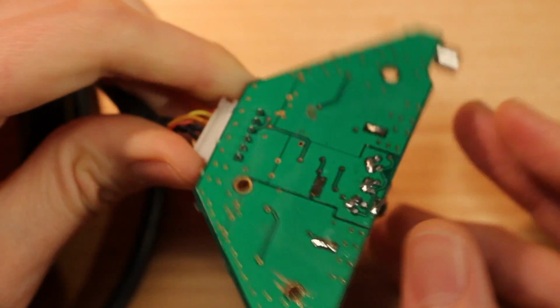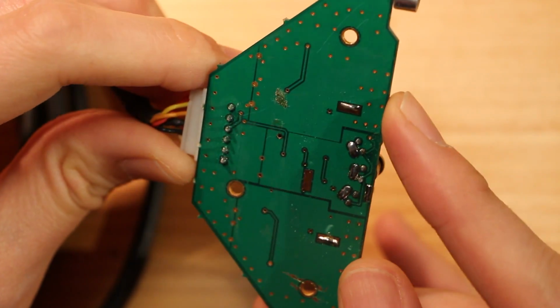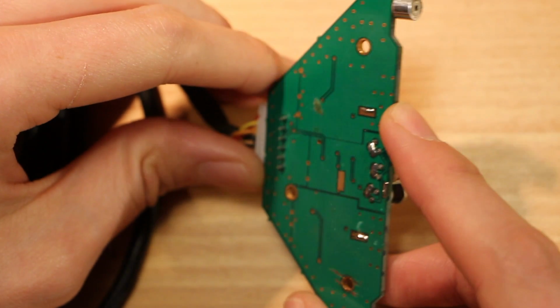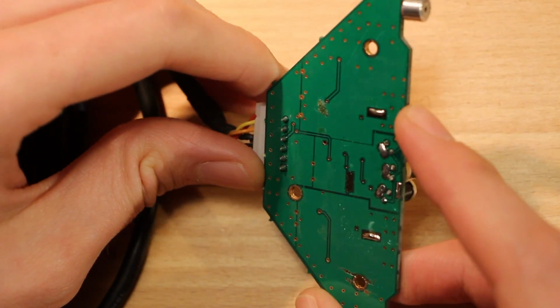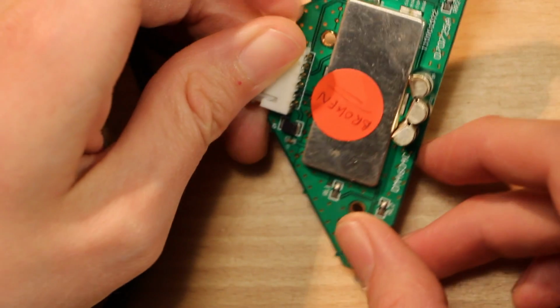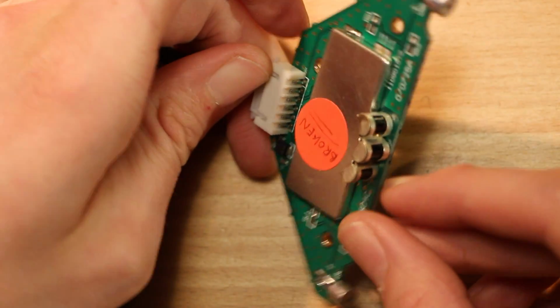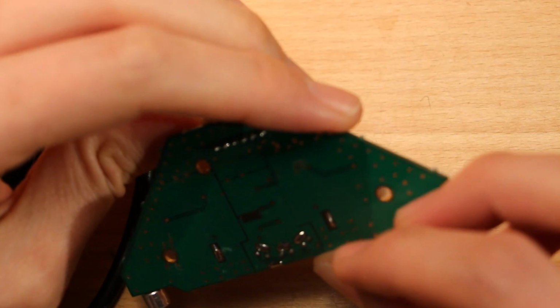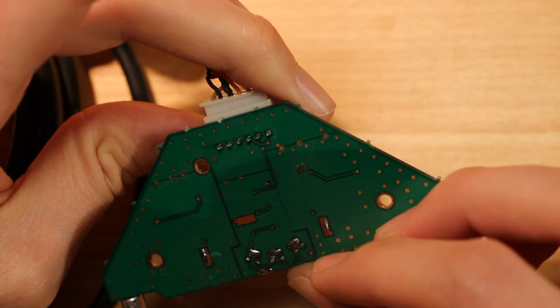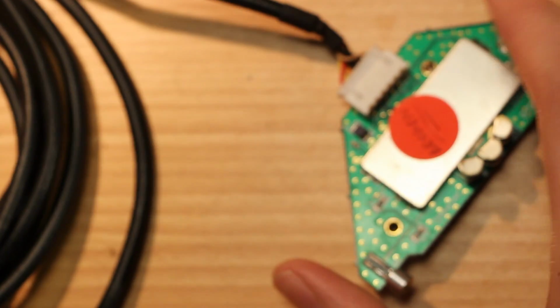So I suspect that the sensitivity of the light sensor is really one of the bottlenecks in this system. They have to really crank up the gain on those amplifiers, and because of that, totally shield the heck out of this thing to prevent radio interference or 50 or 60 hertz hum from mucking everything up.